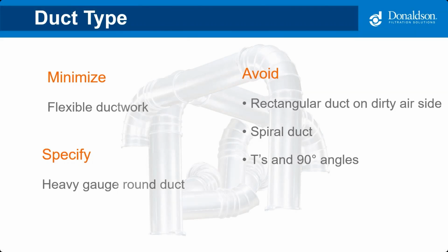Most collection systems and applications will use class 2, 3, or 4 ductwork, which are designed to the SMACNA standards. Spiral duct, one of my least favorite types of duct, tends to leak air and could impact your design of airflow by about 10%. If used outside, it also provides a prime source for water to enter the ductwork and get into the dust collection system. So spiral duct is not recommended. May be the cheapest, but it'll cost down the road.